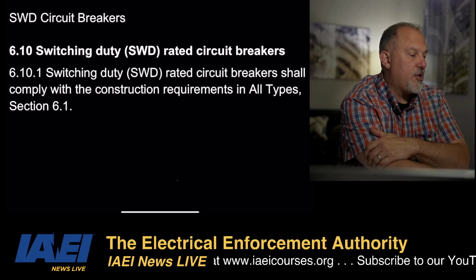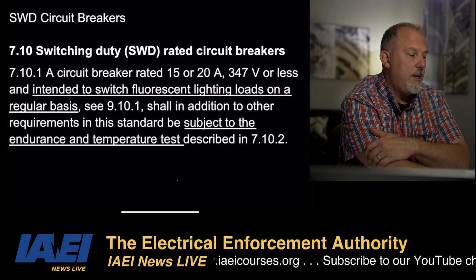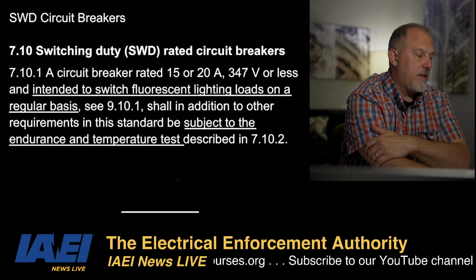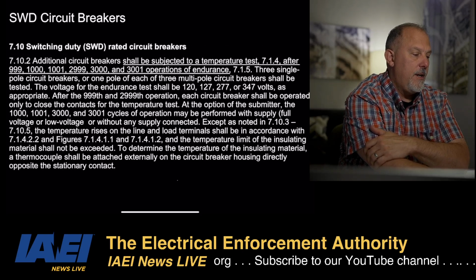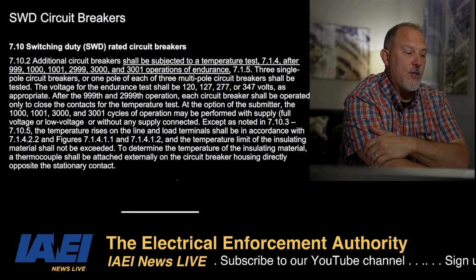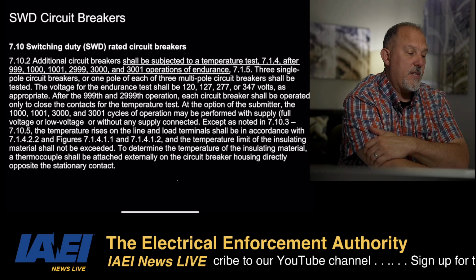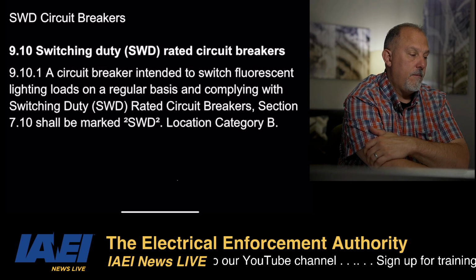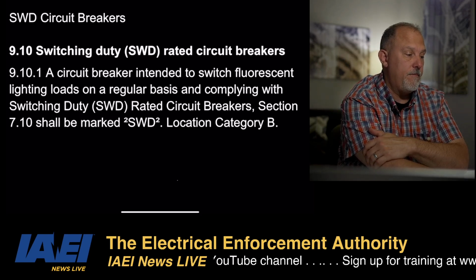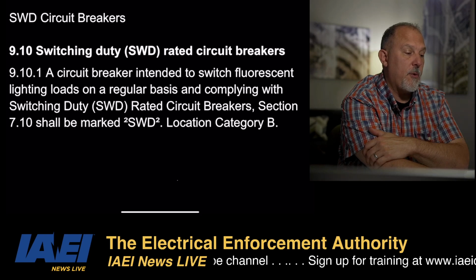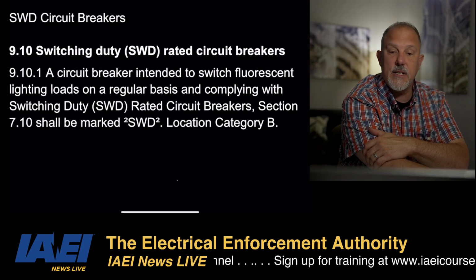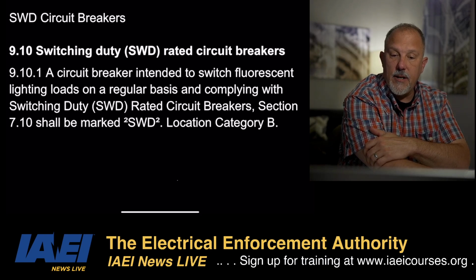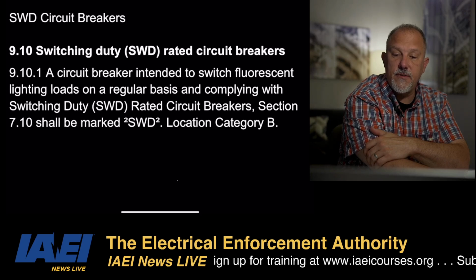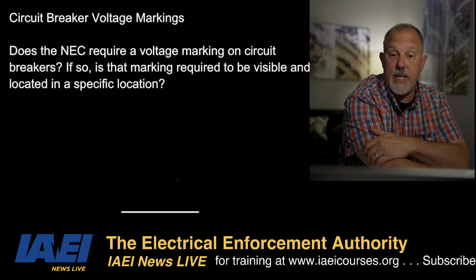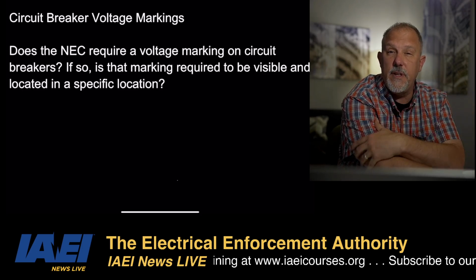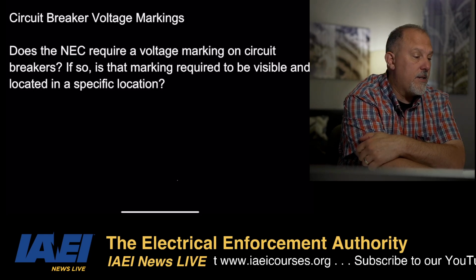Switch duty rated circuit breakers shall comply with the construction requirements, all types. There's your fluorescence, subject to the endurance temperature tests. There's your cycles. I don't have a power factor specified for this, like I had for HID, if you remember that one. Switch duty circuit breakers: a circuit breaker intended to switch fluorescent lighting loads on a regular basis and complying with the switch duty rated circuit breaker section 7.10 shall be marked SWD, location category B. Remember, I can make it so you have to remove the dead front to see that label. All right, so hopefully that answered that question.